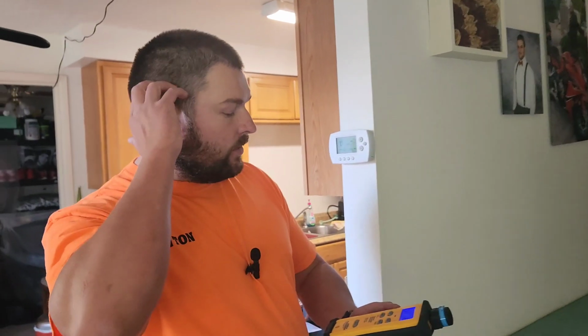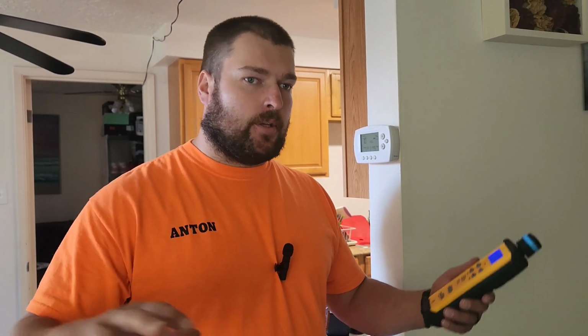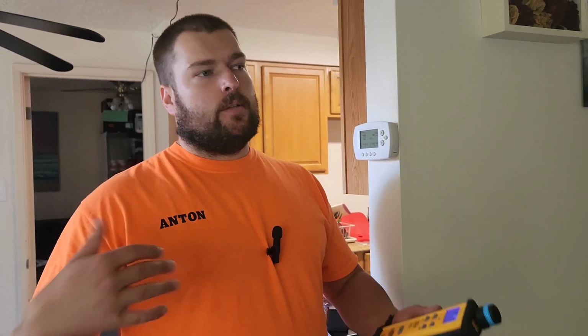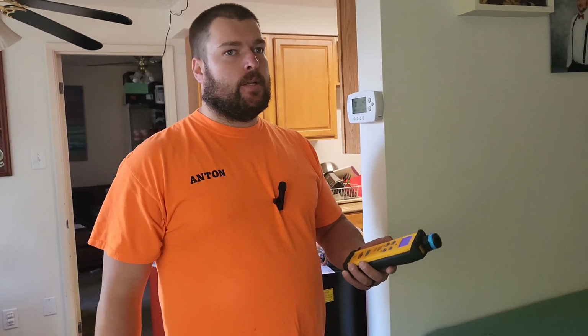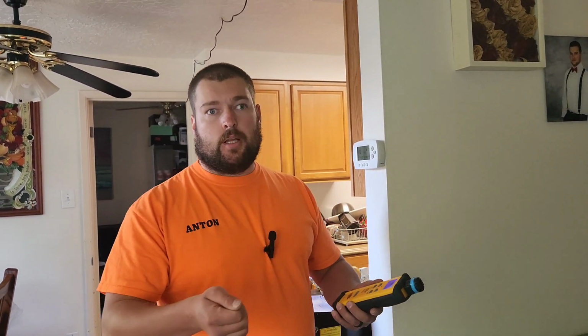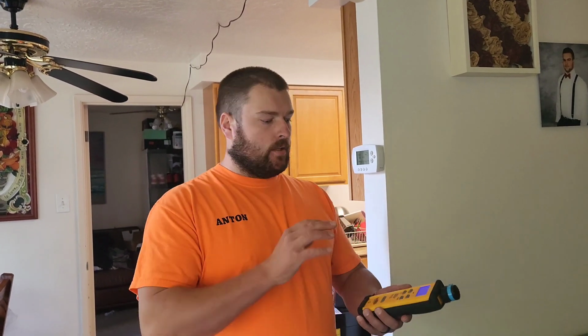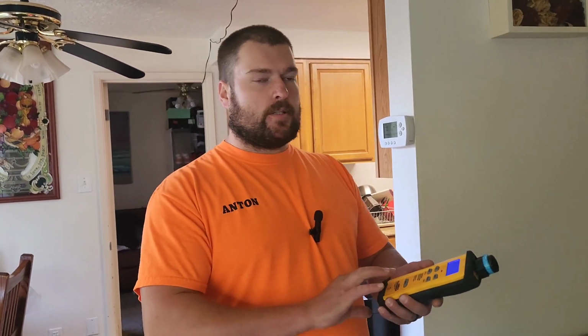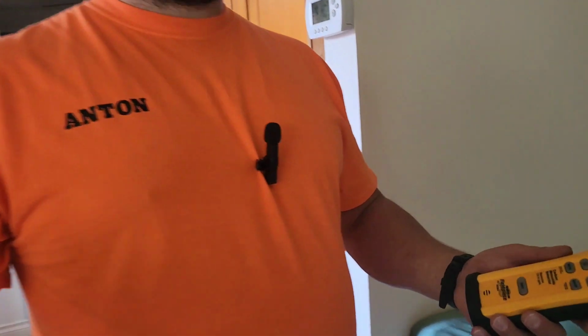So with this meter, as we're walking around and that furnace is on, if we start seeing your parts per million slowly start to rise, that means you have carbon monoxide slowly accumulating in your home, then that's a big red flag that that heat exchanger is compromised. And we can confirm that with a combustion analyzer test, just testing the furnace. The reason I like this test is because we're testing the whole envelope of the home. Some homeowners will have a gas fireplace or a gas water heater, so we're testing pretty much every combustion appliance.